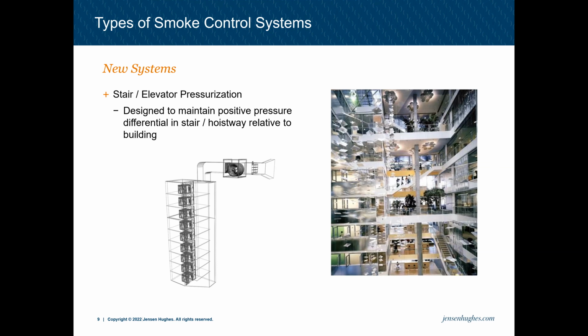years ago, because people need to egress through these stairs. These stairs are how people are getting in and out of a building during a fire event, and smoke going into our stairwell, or being passed to different floors through our elevators, causes issues for our occupants on the higher levels before they can get out of the building. Stair and elevator pressurization is designed to maintain a positive pressure in your stair or hoistway relative to the building. They're mostly required in high-rise buildings and underground buildings.